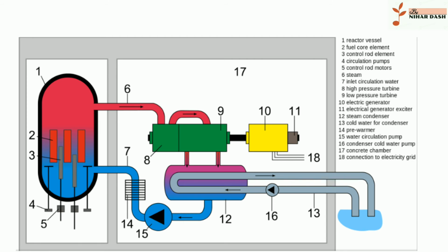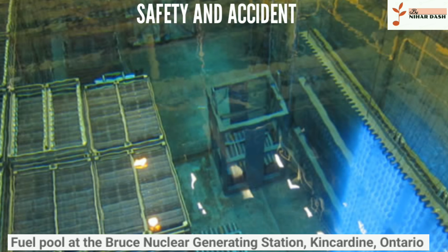For boiling water reactors, continuous power supply to the reactor is critical to ensure safe operation. Most nuclear stations require at least two distinct sources of off-site power for redundancy. These are usually provided by multiple transformers that are sufficiently separated and can receive power from multiple transmission lines. In addition, in some nuclear stations, the turbine generator can power the station's loads while the station is online, without requiring external power. This is achieved via station service transformers which tap power from the generator output before it reaches the step-up transformer. Safety and accidents.